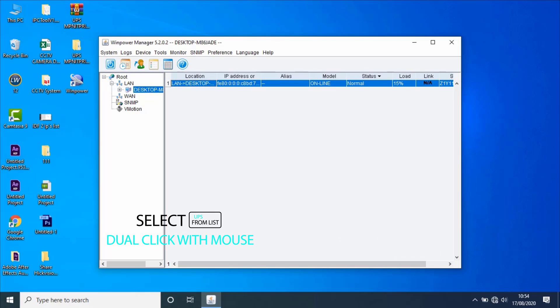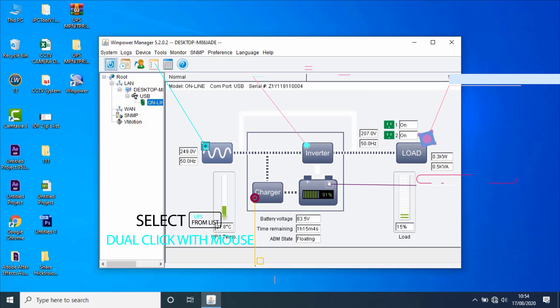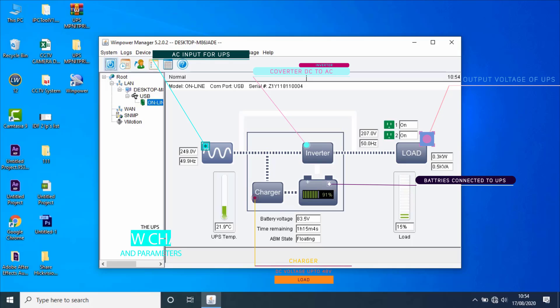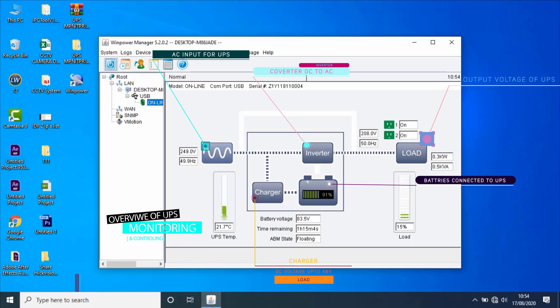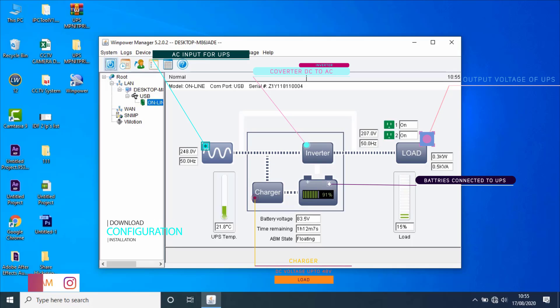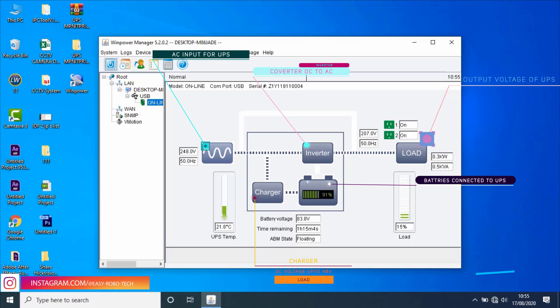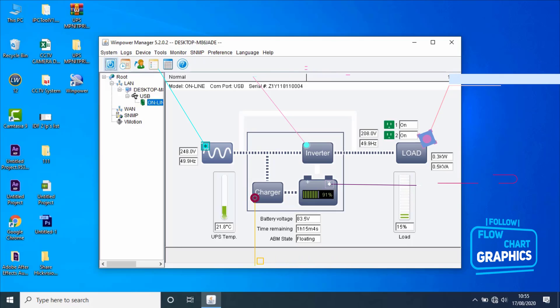Let's select the UPS from the list and double-click on it. A new interface screen with a UPS block diagram will open. In this window, the UPS flow chart and UPS parameters will be shown. Here you will have a detailed overview of the UPS for monitoring, such as input voltage, frequency, battery charging percentage, battery input voltage, backup remaining time, internal temperature, output load, number of outputs on, and output voltage.